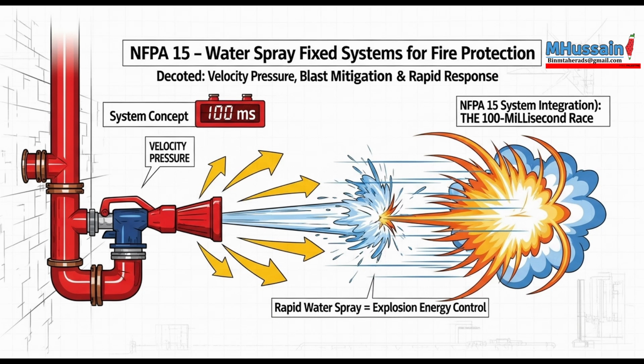Oh, much more. Given the unique, sometimes experimental nature of the hazards NFPA 15 covers, the standard only provides the minimum requirements. The qualified person, the engineer, has to use independent professional judgment. They need proven competence and capability, as defined back in 3.3.18. So it demands a deep understanding. The chemical process, structural loading, fluid dynamics, everything. Absolutely. If you propose an alternative solution, or if you push the hydraulics near the limit, that RPE signature is basically proof that someone with the highest level of competence has looked at it and accepted the risk involved.